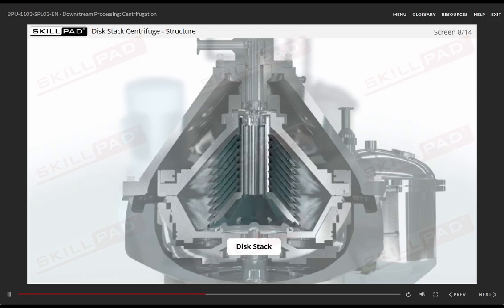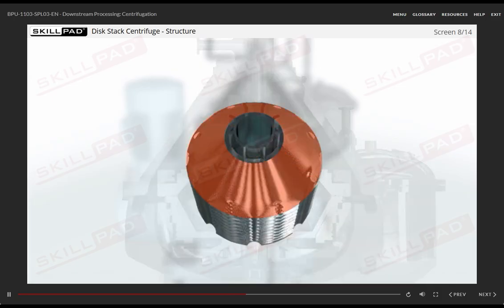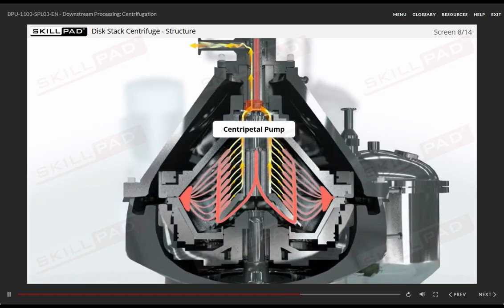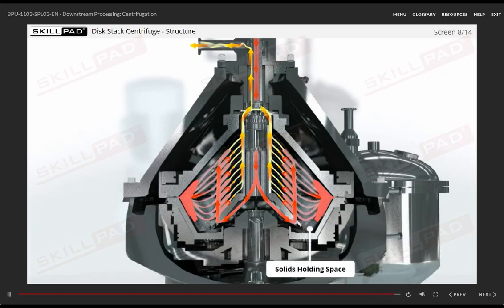The discs in the disc stack are positioned at an angle as shown on screen. Although they are relatively short, they have a high surface area, which shortens the sedimentation path and increases the efficiency of the centrifuge. A centripetal pump located at the top of the centrifuge removes the clarified liquid. Solid material that has entered the disc stack gathers on the surface of each disc and then slides down to the solid's holding place at the edge of the bowl.